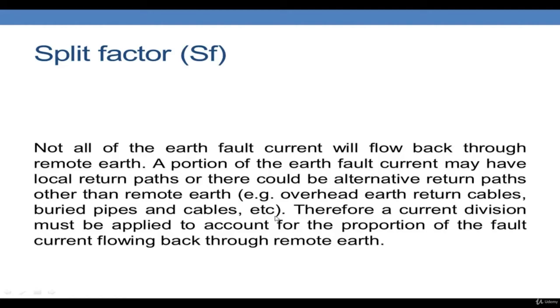Then the next term is the split factor. Not all the fault current will flow back to the earth. A portion of the earth fault current may have other return paths. As a result, the current gets divided at the point of fault, and some of the fault current would go through the overhead earth return cables, buried pipes, and earth conductors, and therefore the current division must be applied to account for the proportion of the fault current flowing back to the remote earth. So in many cases we consider the split factor to be 100%. We consider that all the fault current is flowing to the earth, but in actual cases there will be a split of the current, and some of the current will flow through the earth conductors and the other part will flow to the earth.